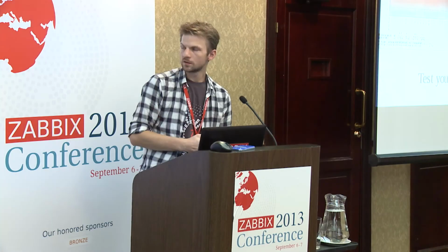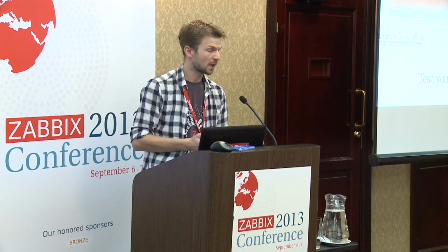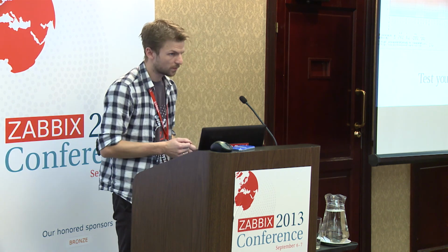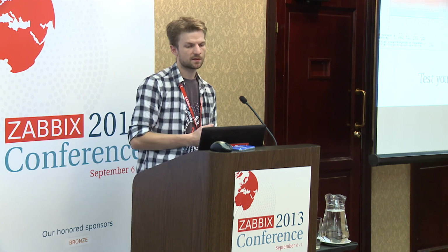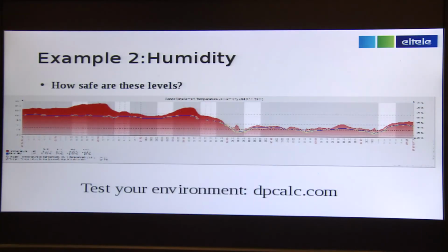A little bit more in depth about humidity. Question: how safe are these levels? First, most of you have probably noticed the technical specification for any component or complete server we have bought. It says operating humidity range, usually something like 5 to 95% relative humidity, non-condensing.